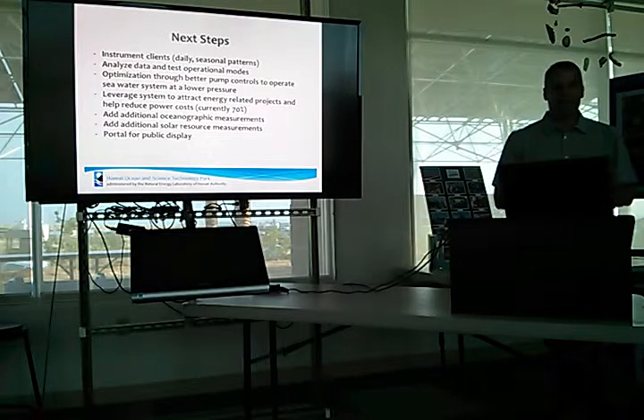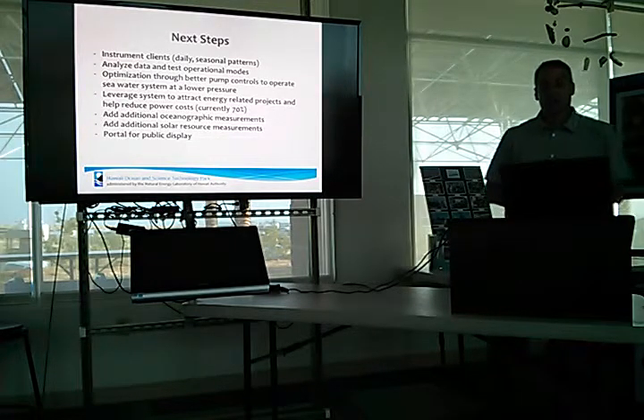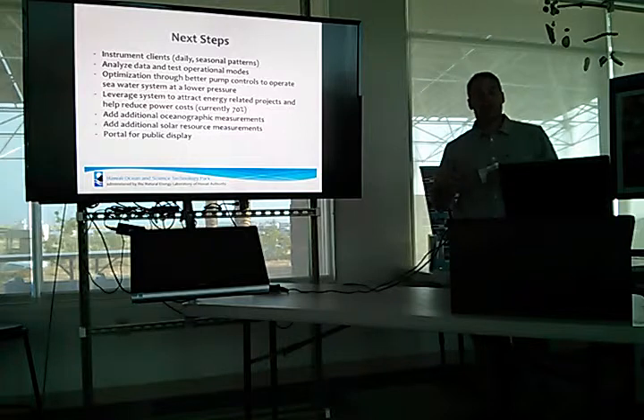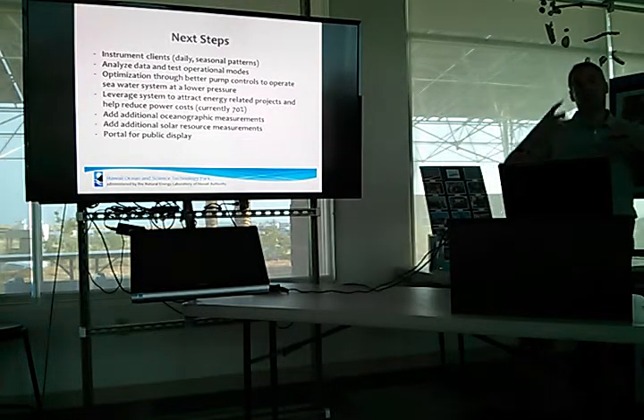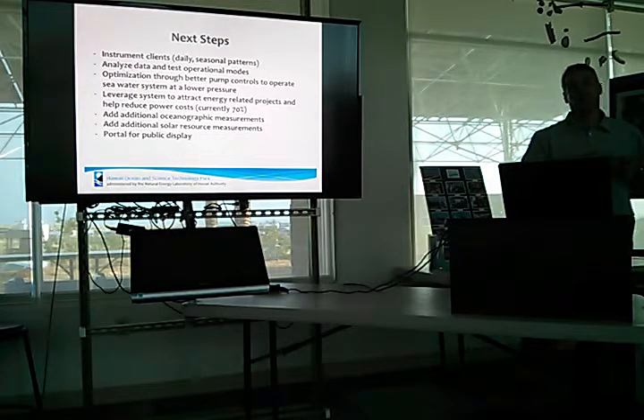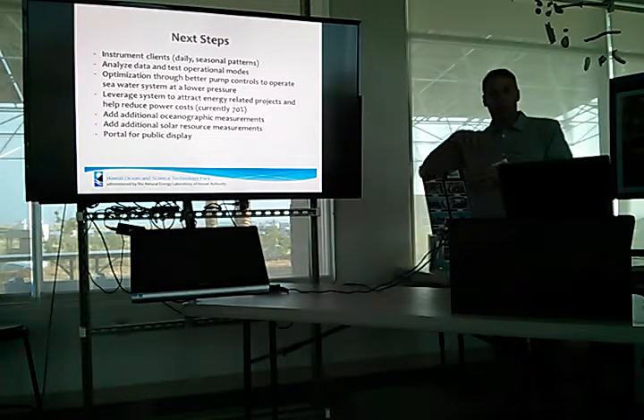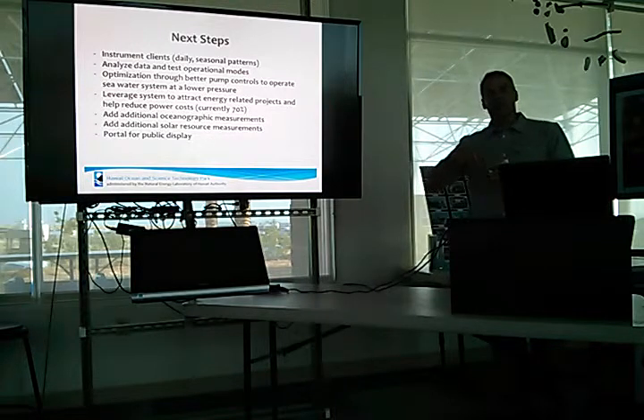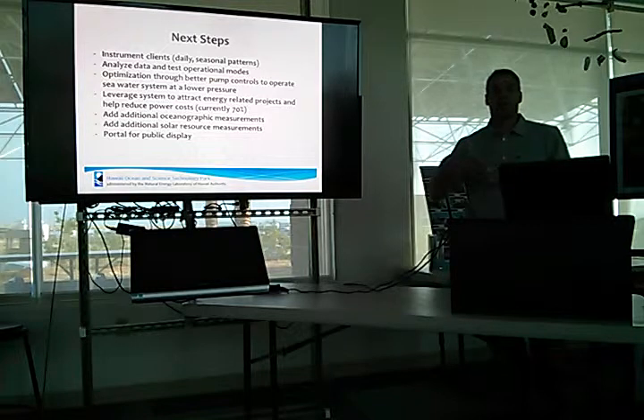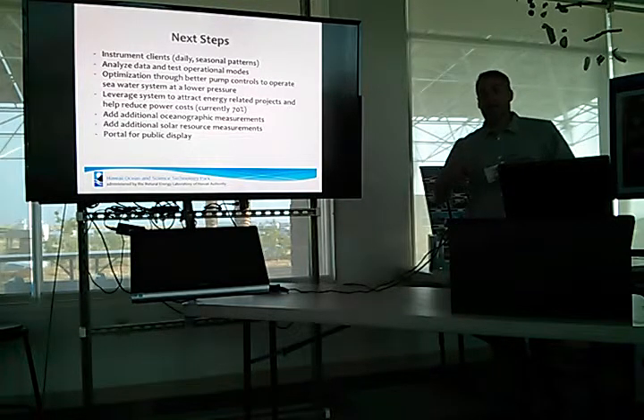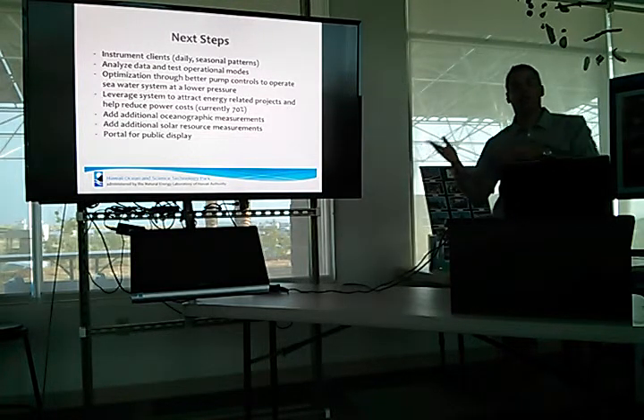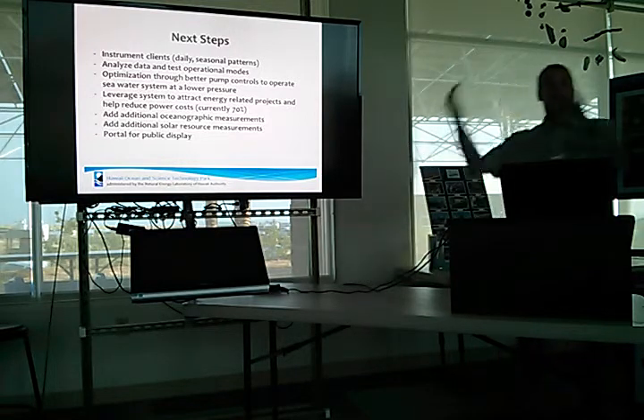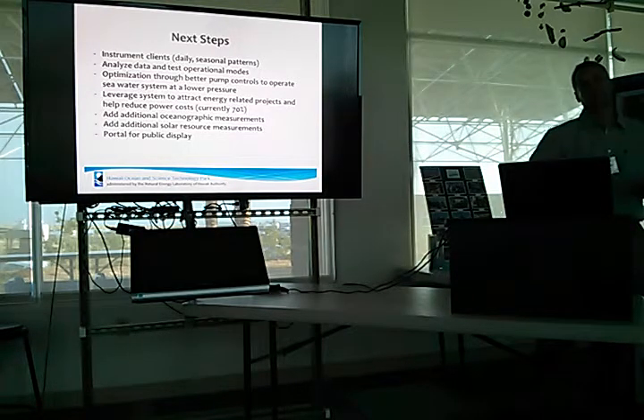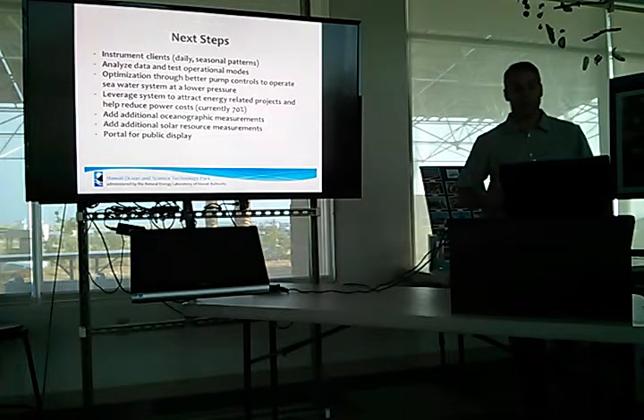So, next steps: we'd like to instrument our clients so we can understand their daily and seasonal patterns. We currently have old paddle wheel flow meters, and we're going to try to move over to what we call mag meters. They don't have moving parts, so we'll have fewer problems with biofouling and other issues we've had over time. We also want to bring that signal back into the SCADA system so we have real-time data to share with our clients.